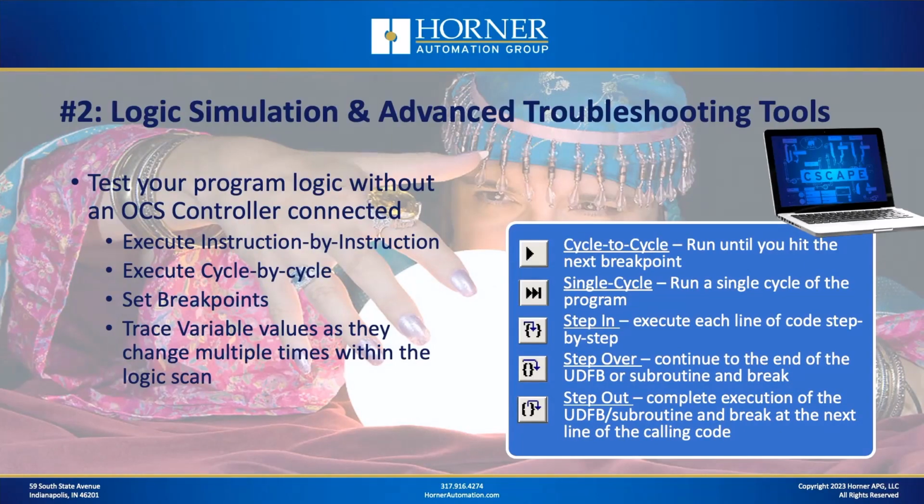So that can be a real benefit, especially if your code is a little bit complex and you have something that you're struggling getting just right. There are some tools that are available that can be really nifty. For instance, you can execute instruction by instruction if that's going to help you troubleshoot. You can execute one scan at a time and see what's going on at the end of each scan. You can set breakpoints in your logic, okay, and say, what happens up through this point in the logic when I stop here.